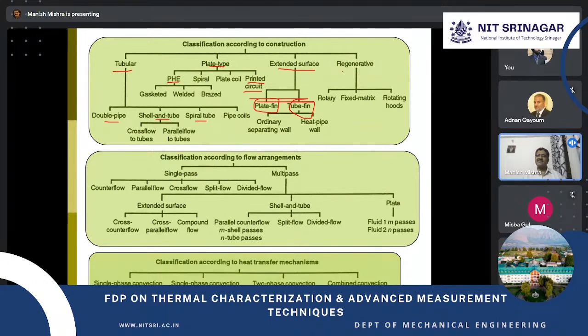Finally there is the regenerative heat exchanger. Regenerative comes based on the mode of heat transfer, though I'm also considering it in construction, because it works on the principle of regeneration. One fluid enters and moves over a solid surface, generally a matrix surface or porous media, which acts as thermal storage. The fluid passes through that for a certain time.